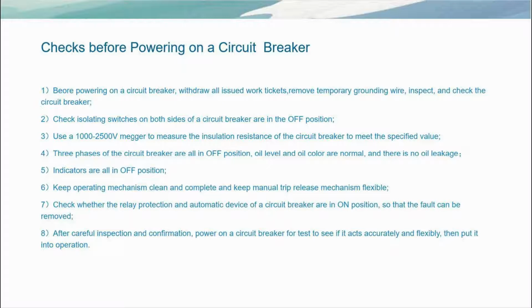6. Keep operating mechanism clean and complete and keep manual trip release mechanism flexible. 7. Check whether the relay protection and automatic device of a circuit breaker are in on position, so that the fault can be removed. 8. After careful inspection and confirmation, power on a circuit breaker for test to see if it acts accurately and flexibly, then put it into operation.